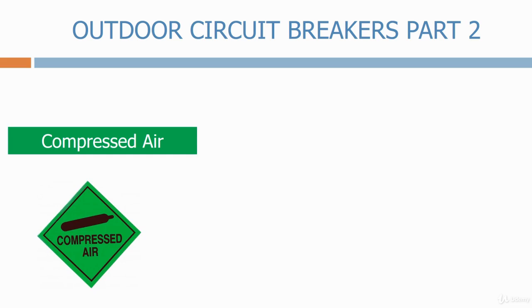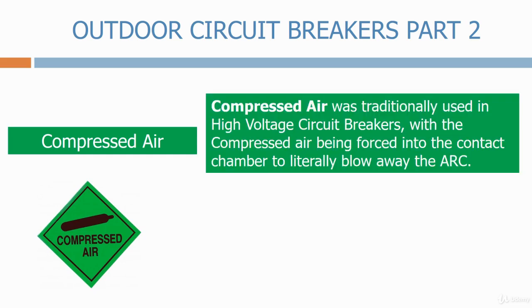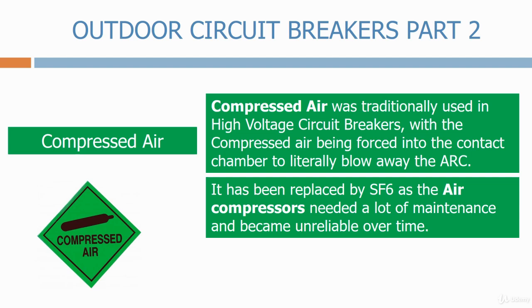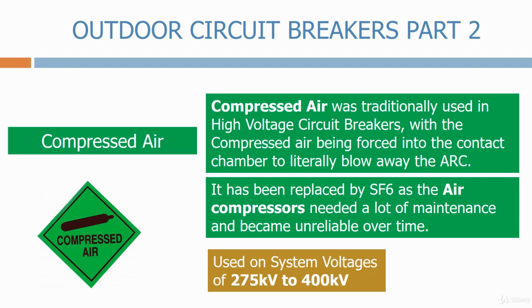Compressed air. Compressed air was traditionally used in high voltage circuit breakers, with the compressed air being forced into the contact chamber to literally blow away the arc. It has been replaced by SF6, as the air compressors needed a lot of maintenance and became unreliable over time. Used on system voltages of 275 kV to 400 kV.